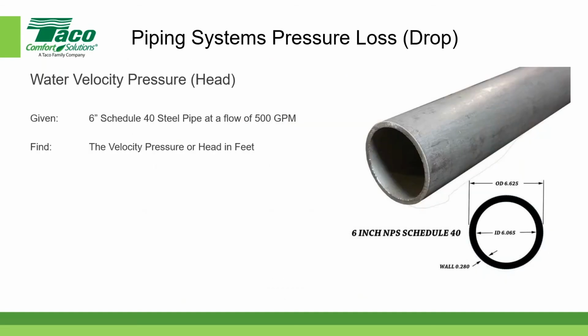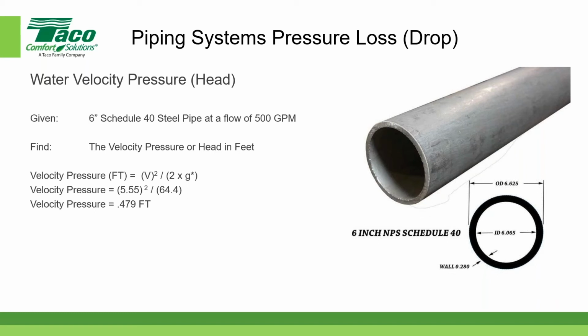All right, so the next piece of information, which is also useful, is to figure out what the velocity pressure is. Given a 6-inch schedule 40 steel pipe at a flow of 500 gallons per minute, the velocity pressure or head in feet is equal to the velocity squared divided by 2 times the gravitational constant. We just said that the velocity was 5.55 feet per second. The gravitational constant is 32.2, so that's 5.55 squared divided by 64.4, and you'll find that the velocity pressure is 0.479 feet. The G in this case stands for the gravitational constant of 32.2 feet per second squared.